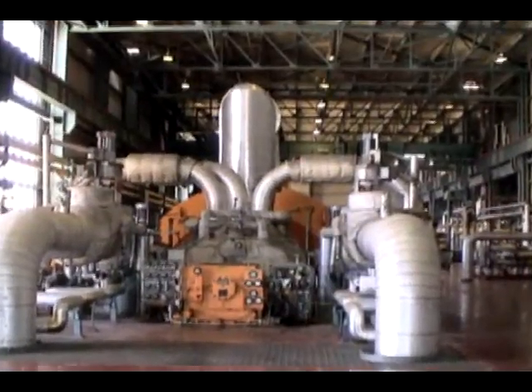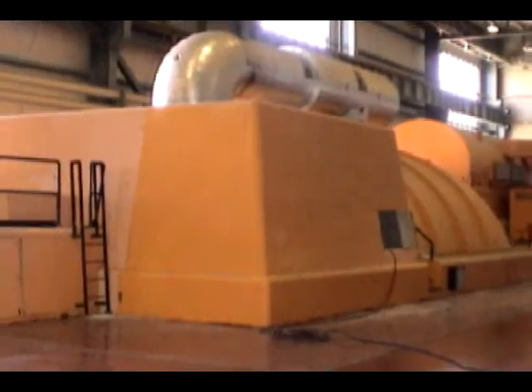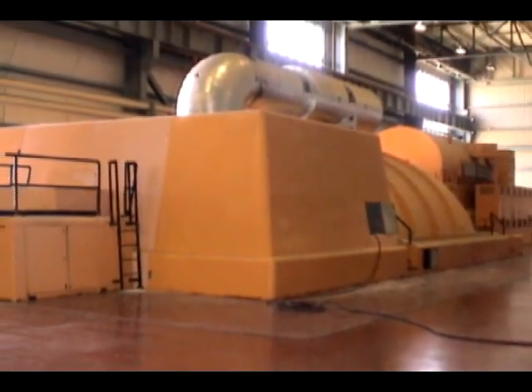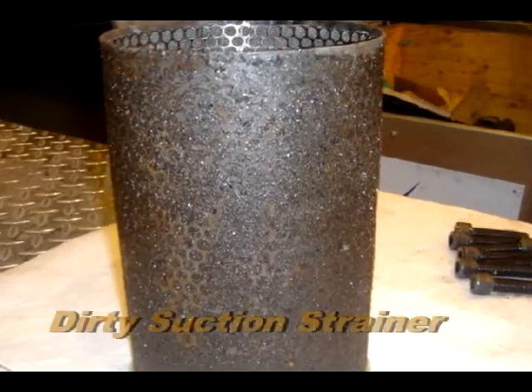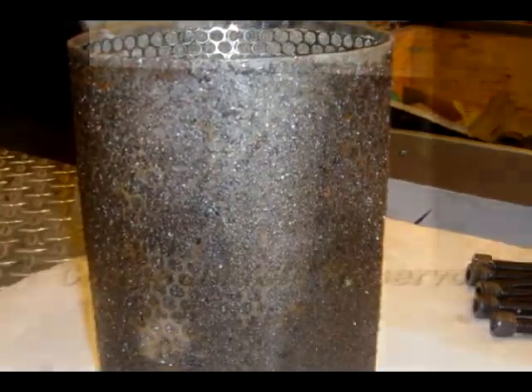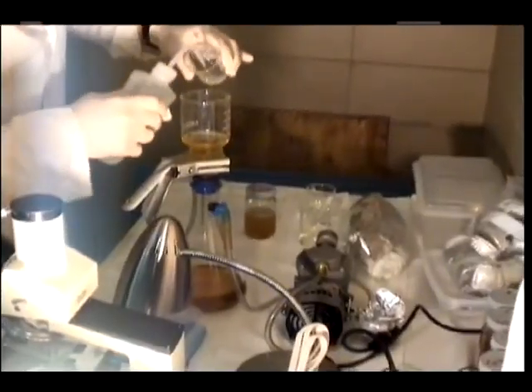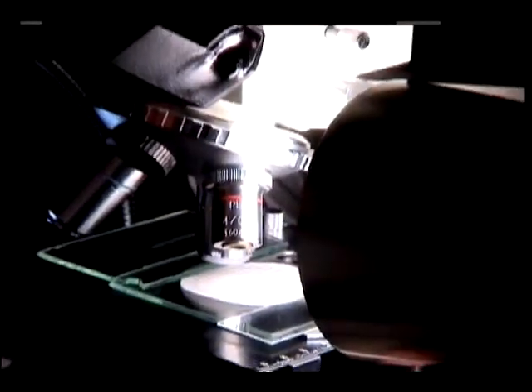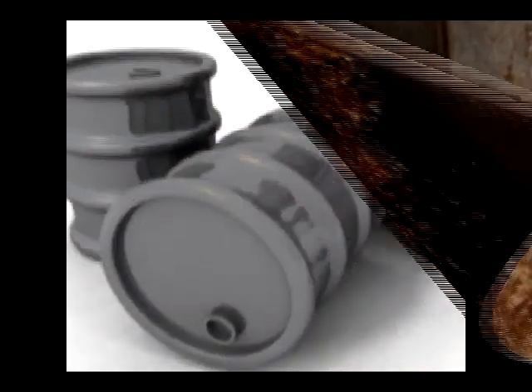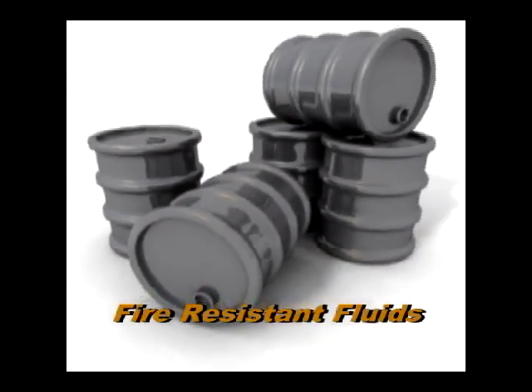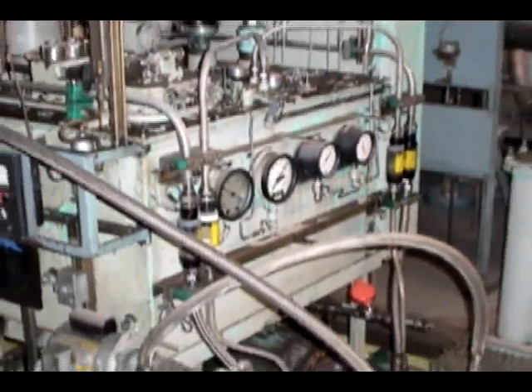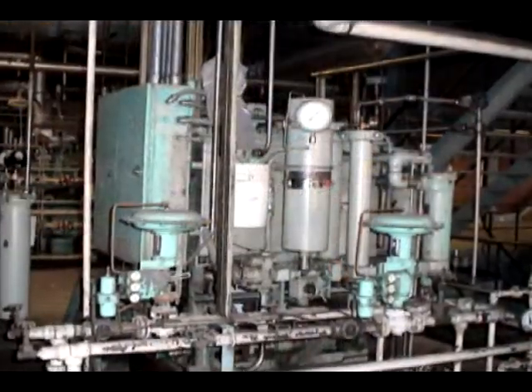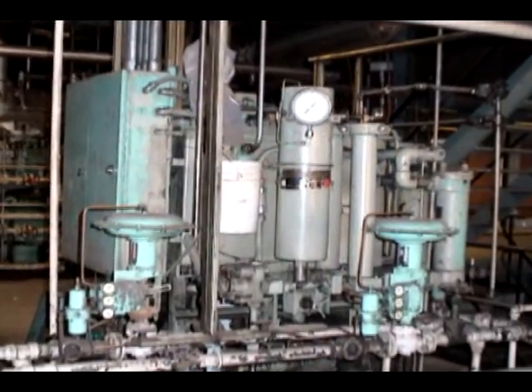These phosphate ester fluids have superior fire-resistant properties and have performed well over the past 40 years. Unfortunately, the phosphate ester fluids are now being blamed for numerous problems experienced in hydraulic fluid systems. Extensive testing conducted over the past few years by numerous independent laboratories have yielded the same conclusions. The major contamination being observed in hydraulic fluid systems is being generated by the FRFs. In order to understand why this is occurring, it is important to understand some of the characteristics of the FRFs.